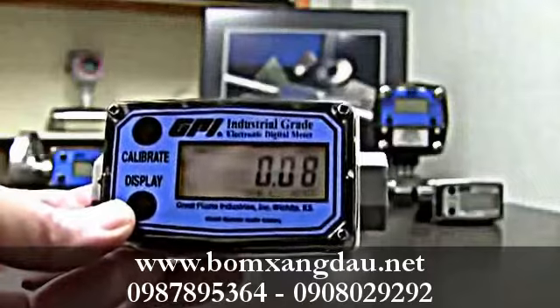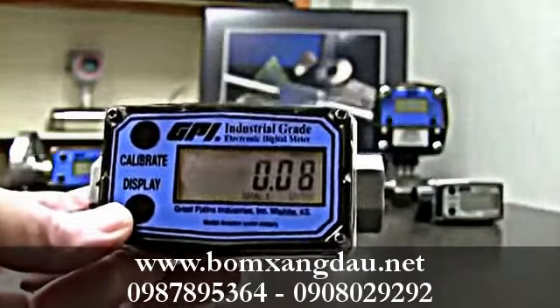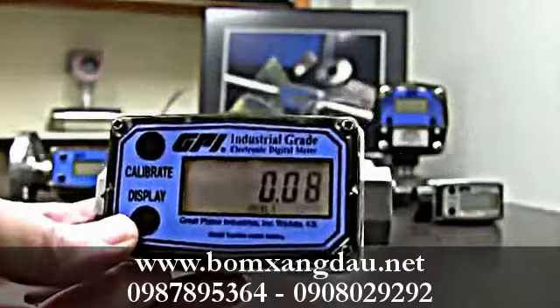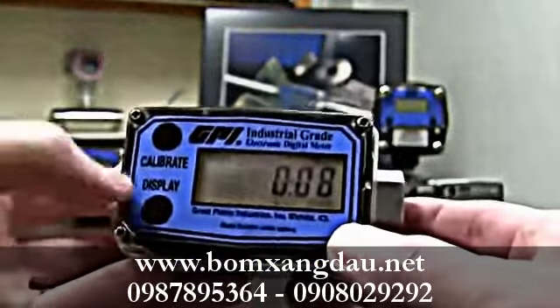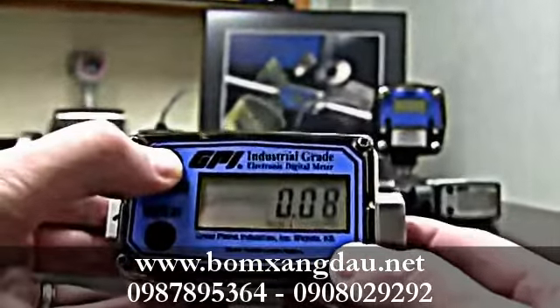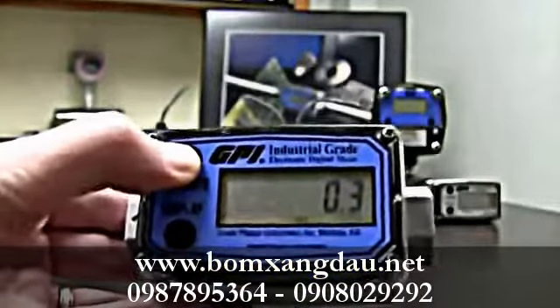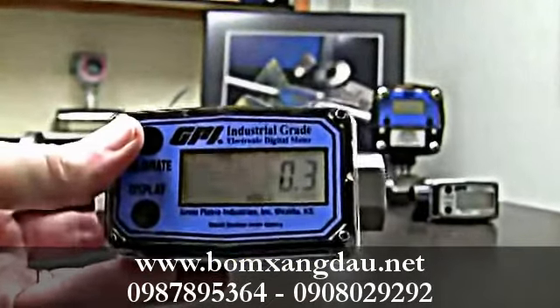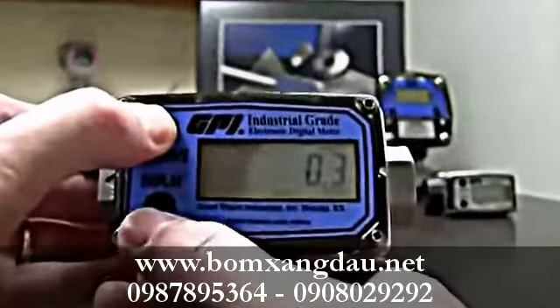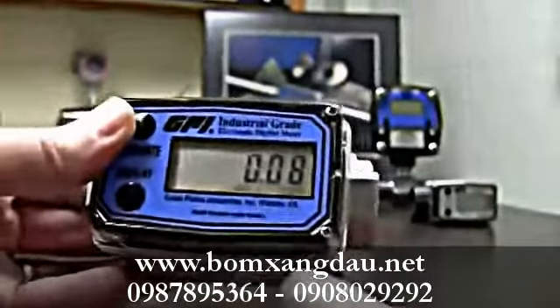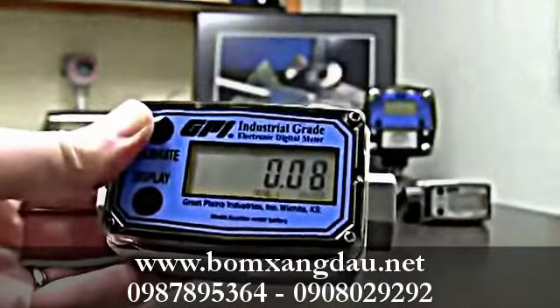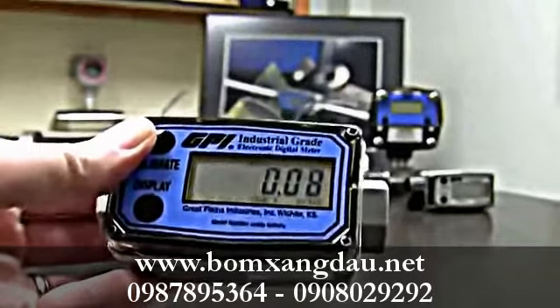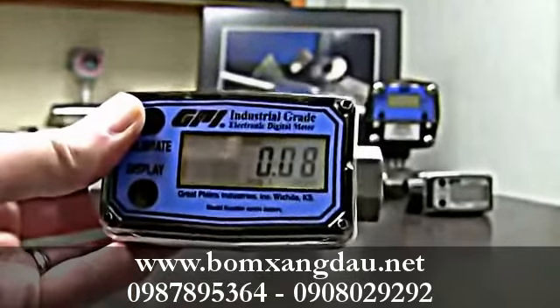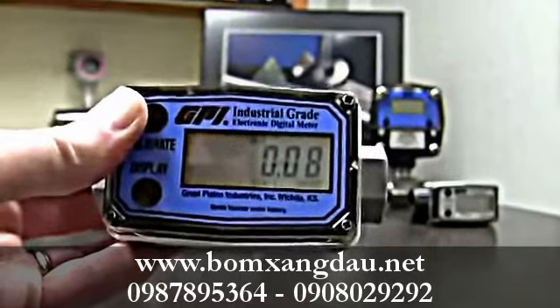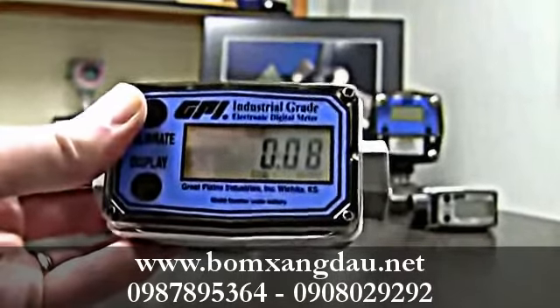Now we have other calibrations that will come along on here. Some of them will have all of these, other ones won't. This one happens to have liters also. Almost all of them will have liters. If you hold down the calibrate button, push and release the display button, it switches to liters preset. Do it again, hold down calibrate, push and release display, and it goes to Cal B. You'll notice now where it says Cal B, the word preset is gone, which means this is not a factory preset, which is something you can change. That's what we're going to talk about today, how to change this calibration.